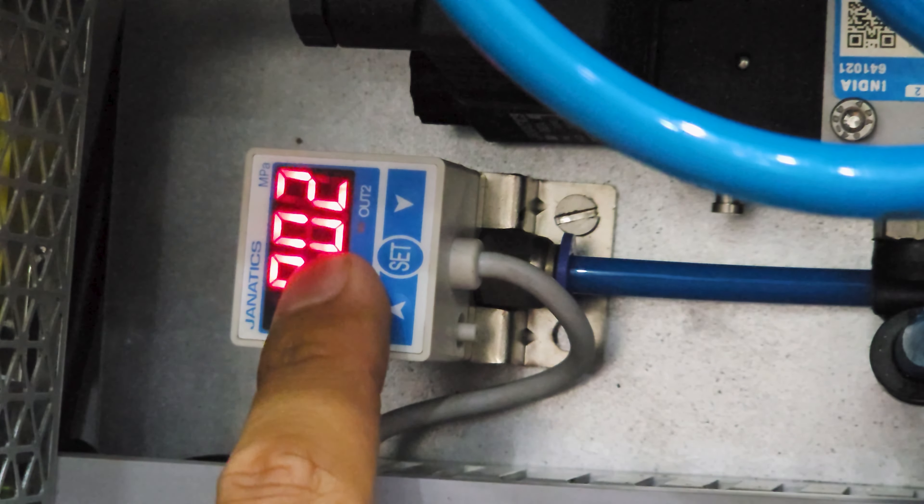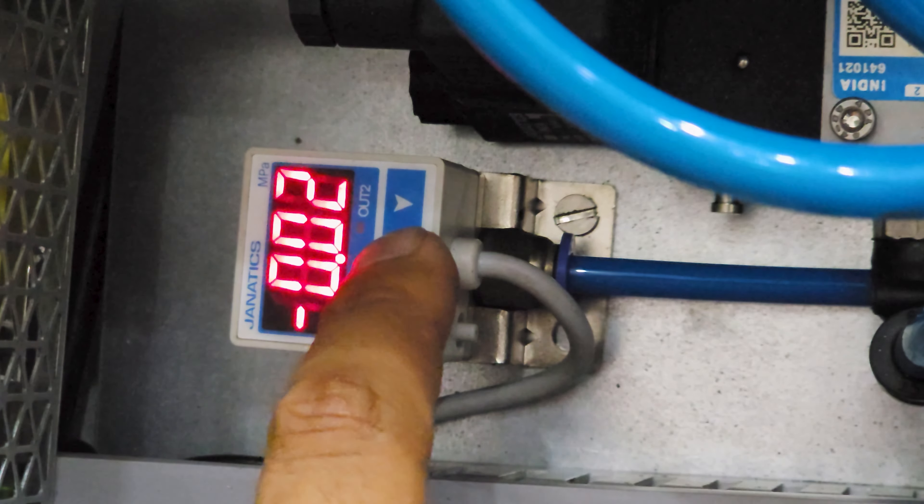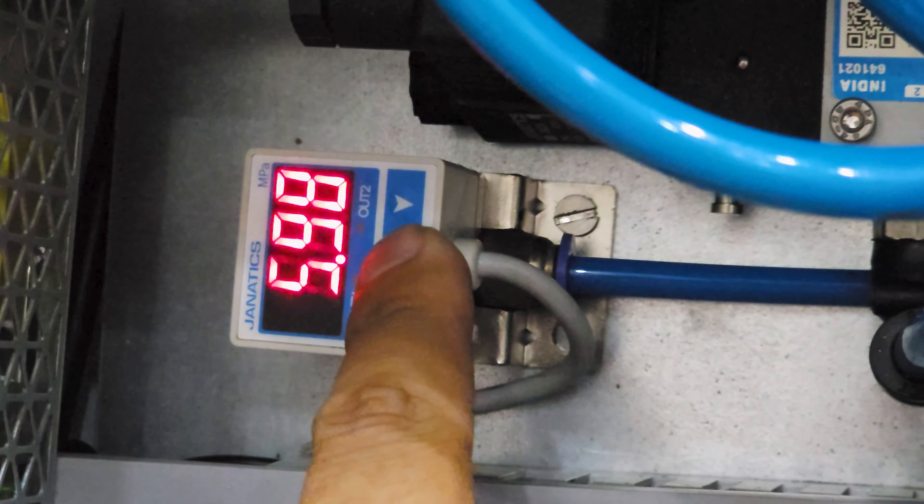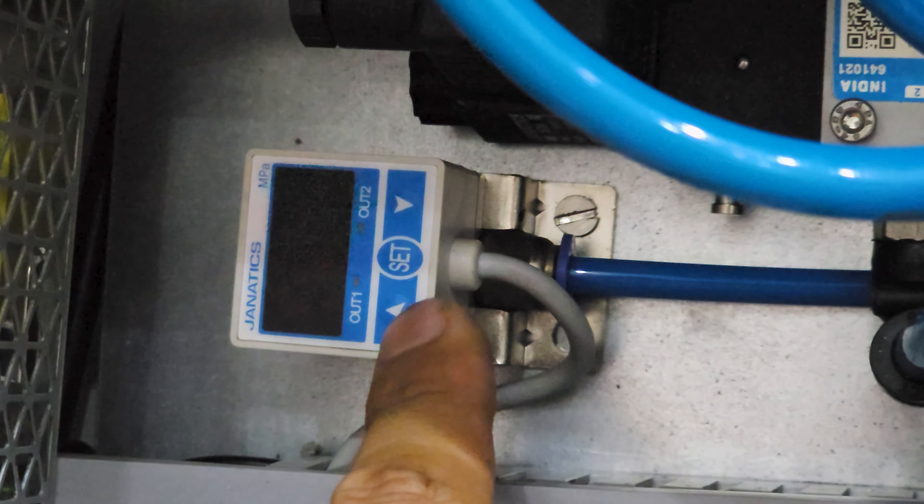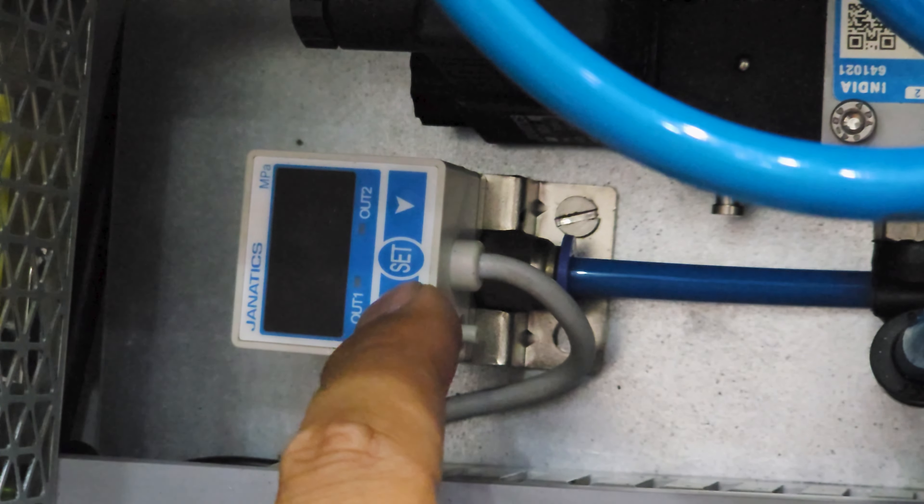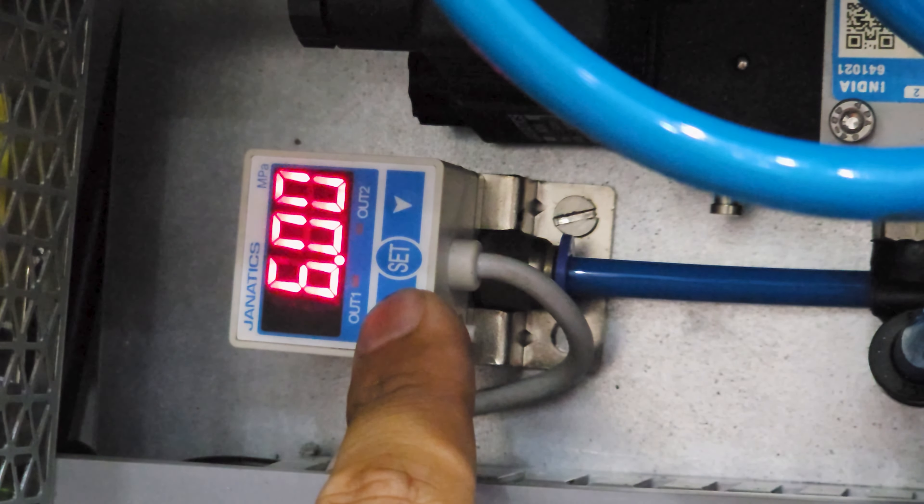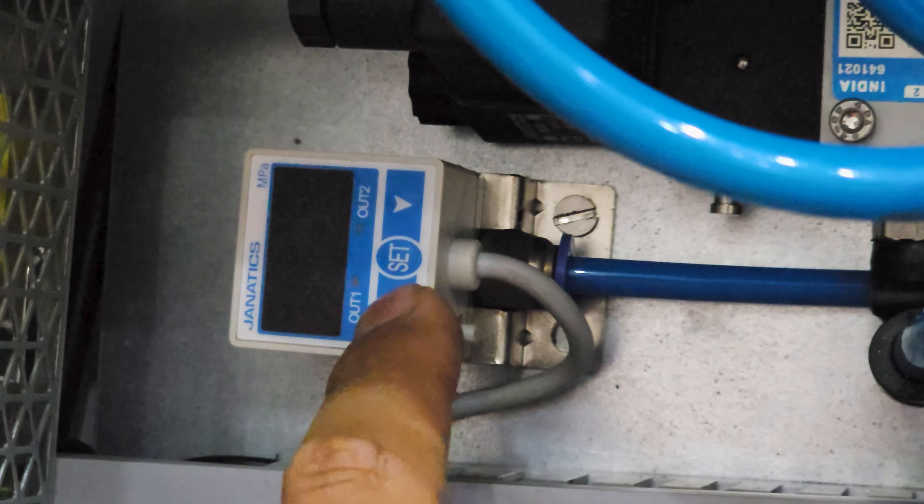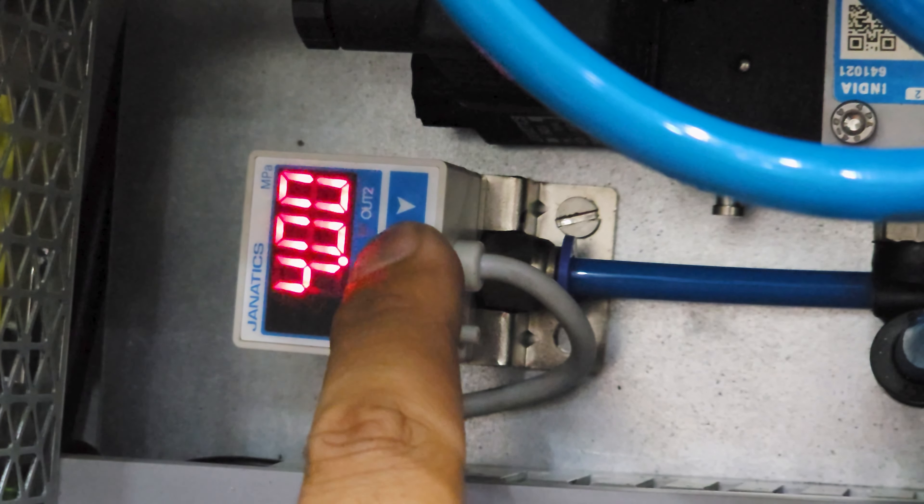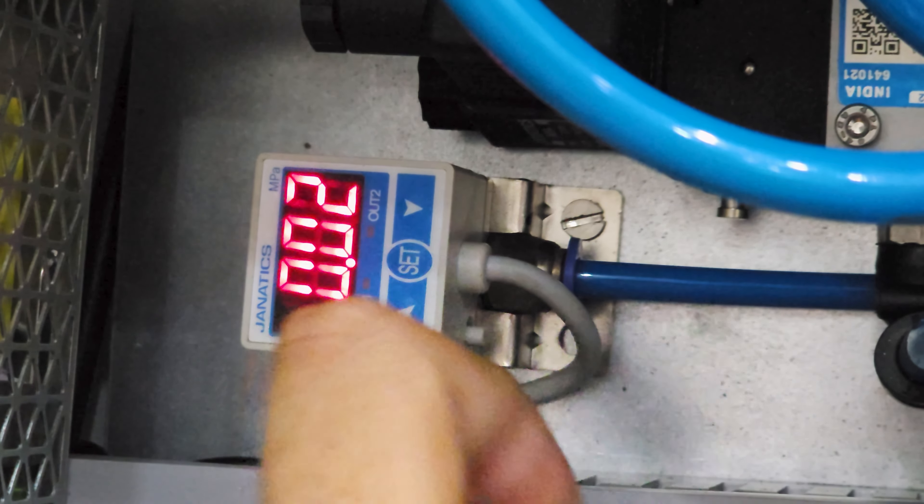Locate the pressure sensor fitted inside the control panel. Press the set button until P1 is displayed on the screen. Use the arrow buttons to adjust the pressure to the desired level. For optimal results, we recommend a pressure of 6 bar. Once the desired pressure is set, press the set button again to confirm the pressure settings and return to the previous screen.